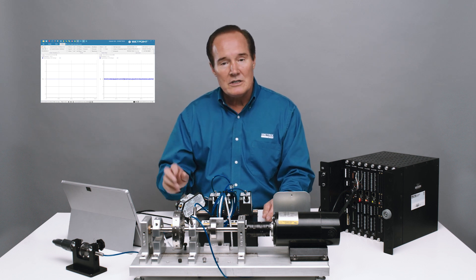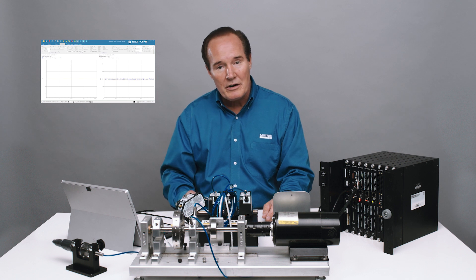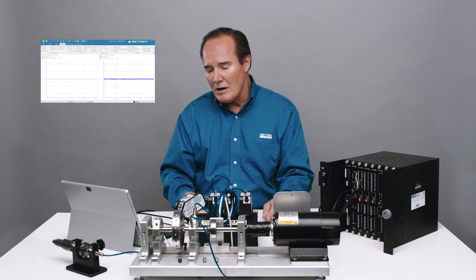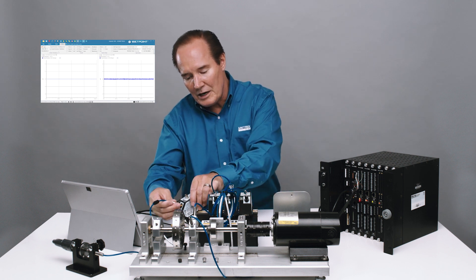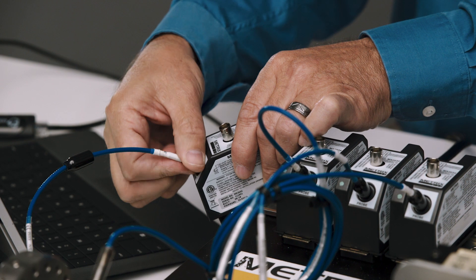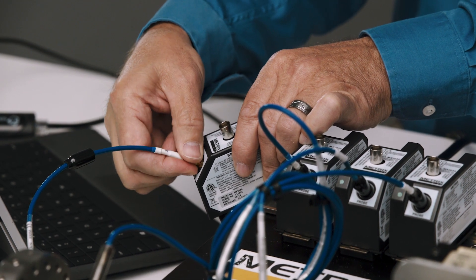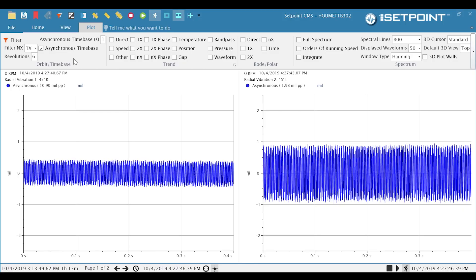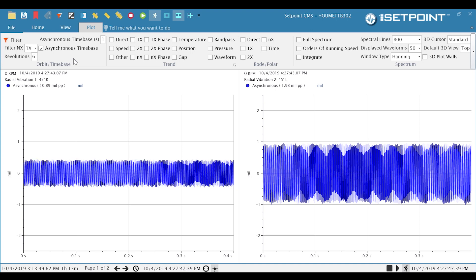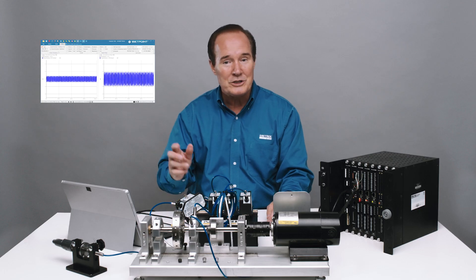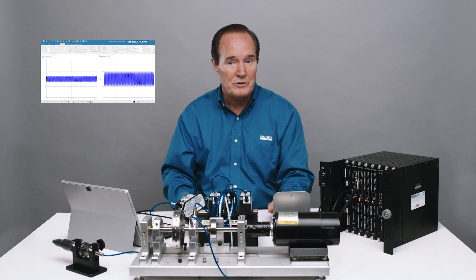Our driver does a little bit better than that, but for a transmitter, 0.2 mils is actually pretty good. Now I'm going to go ahead and connect it back and bring our noise back. That lets you know that we really do have a noise problem. And if you think you have a noise problem at your plant, as long as you've bypassed the channels, you can do the same thing — disconnect the channel, and if your noise problem goes away, you can pretty much know that they're talking to each other.